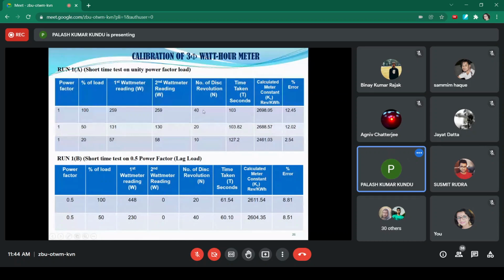The number of disc revolutions for 100% rated current is fixed at around 40. To complete the 40 disc revolutions at 100% load current, the time taken using the stopwatch is 103 seconds. But when the load current is reduced to half, that is 50%, the number of disc revolutions, instead of 40, is reduced to 20. Why? To avoid waiting, 20 revolutions are sufficient to get the reading, and the time taken is 103.82 seconds to complete the 20 revolutions.